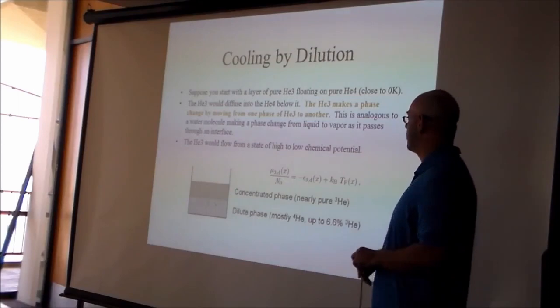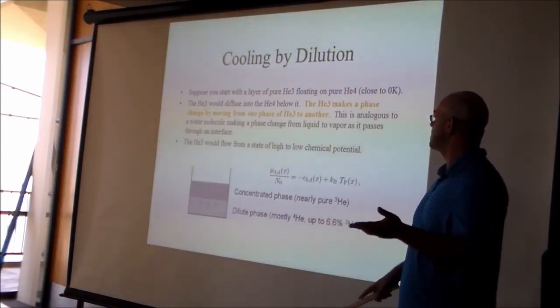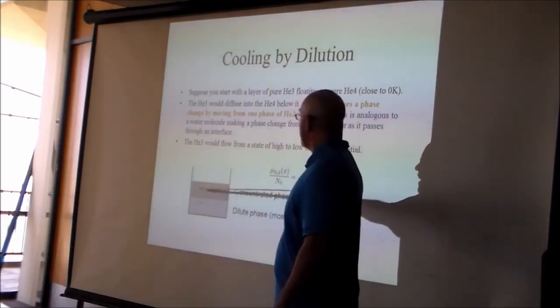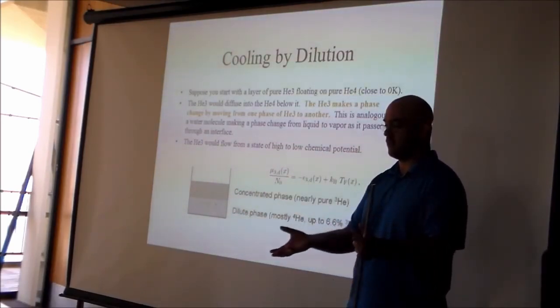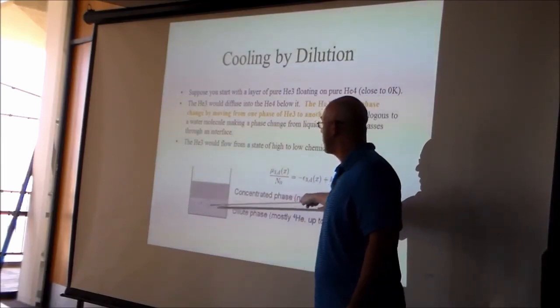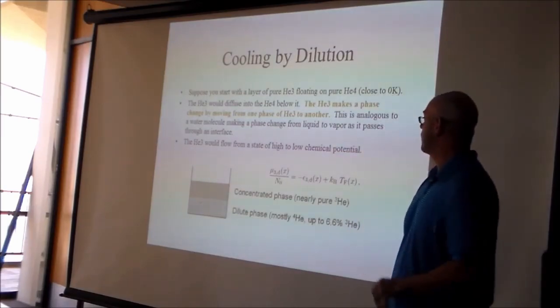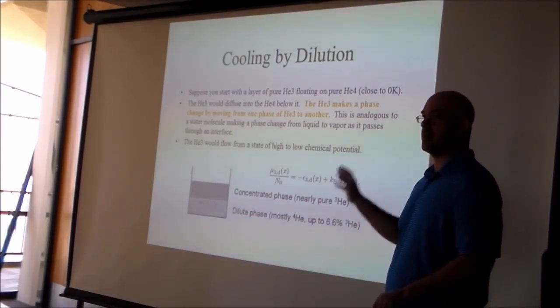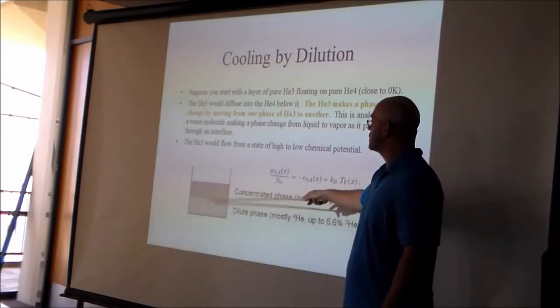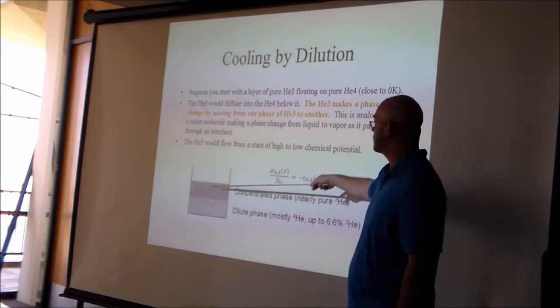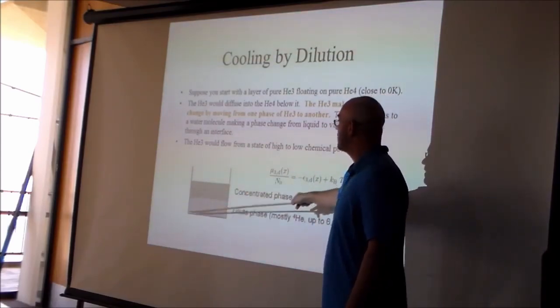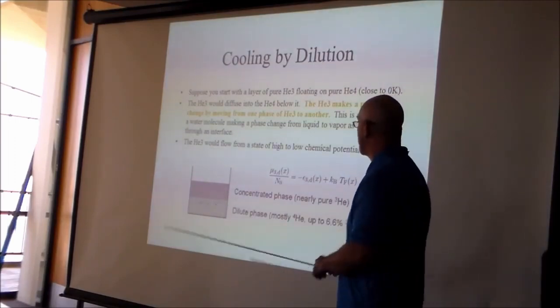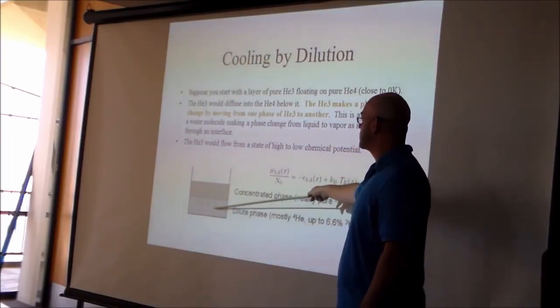Now let's move on to how the dilution refrigerator works. In this thought experiment, imagine a layer of helium-3 sitting on top of helium-4 at T = 0. Helium-4 is denser and sits on the bottom; helium-3 is on top. Helium-3 will begin diffusing into the helium-4. The pure helium-3 layer is called the concentrated phase, and the helium-4 layer with some helium-3 mixed in is called the dilute phase.